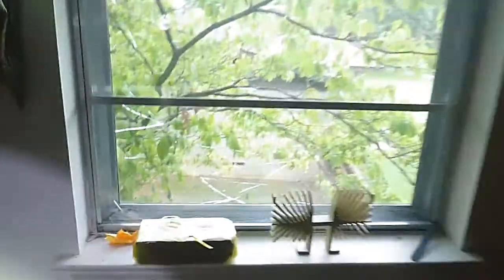This is that dormer. Anytime you see unidentified organic substance or mildew like that, dust around the air supply register, that means the evaporator coils are very dirty. The house faces east, so this would be the north bedroom. The north bedroom window is broken. This is the attic access in the north bedroom closet.